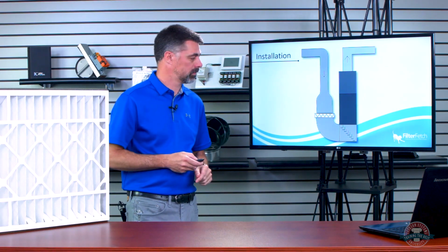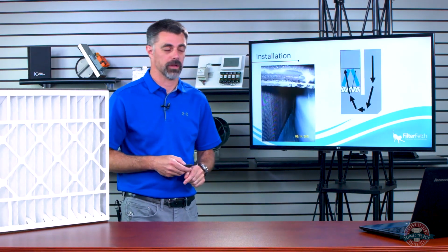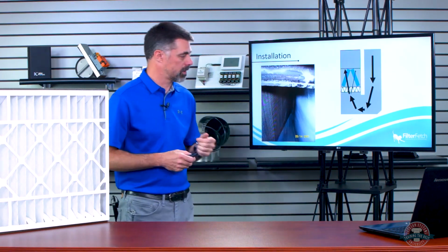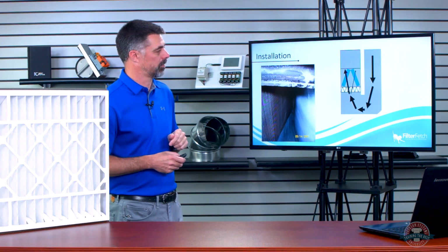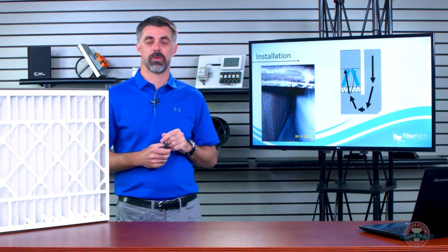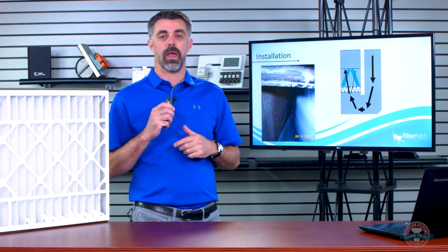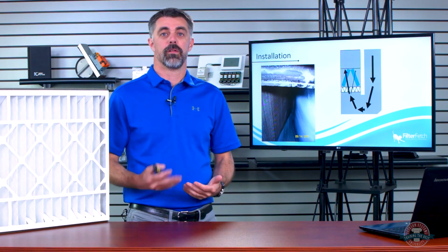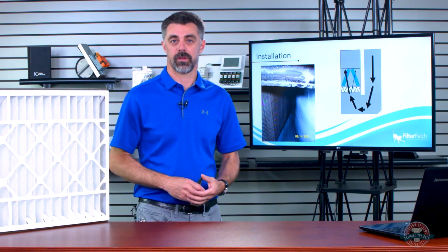Now, let's take a look at this. This was a system that I found years ago. If you look at the date on that, it's been quite some years now. I went out there to service the system, to do maintenance on it, and I found that things were not right. First thing I found was, it looks like it's a little low on charge. So I go inside, I look at the filter.